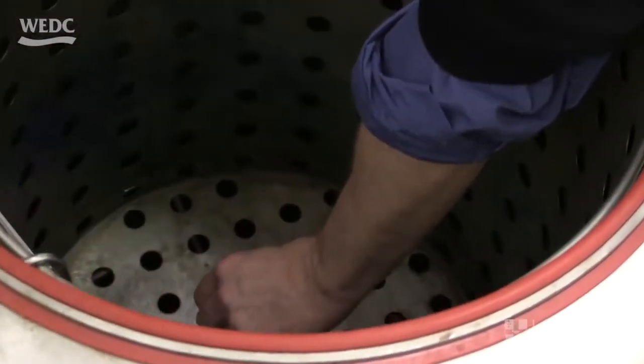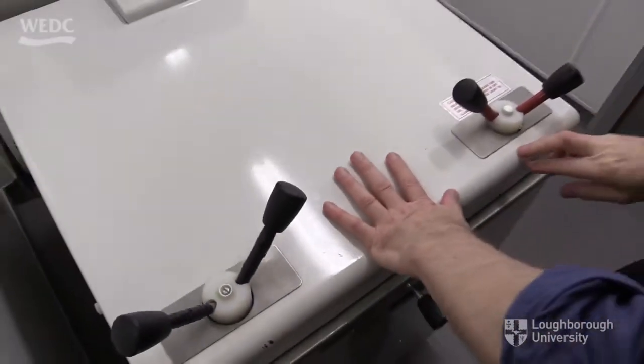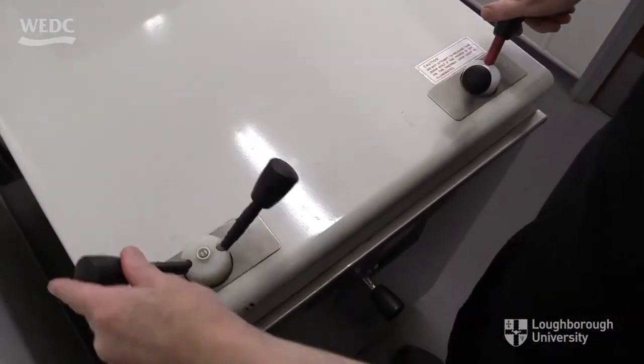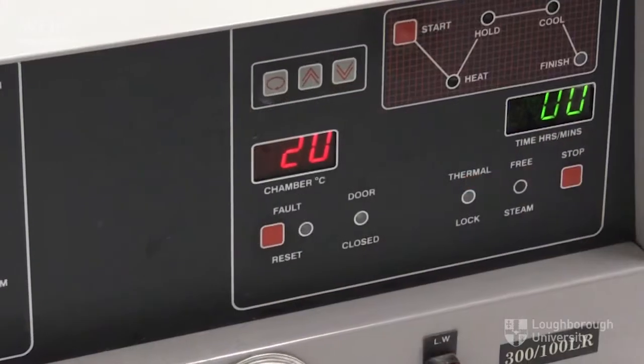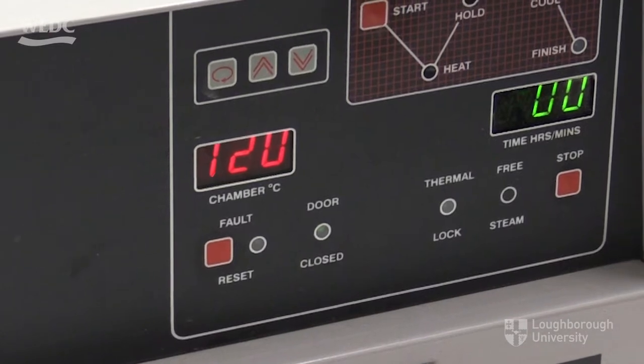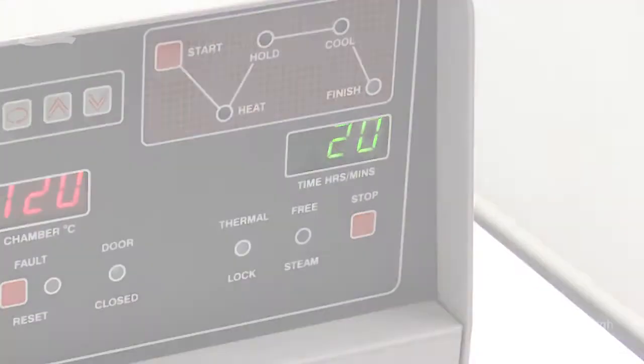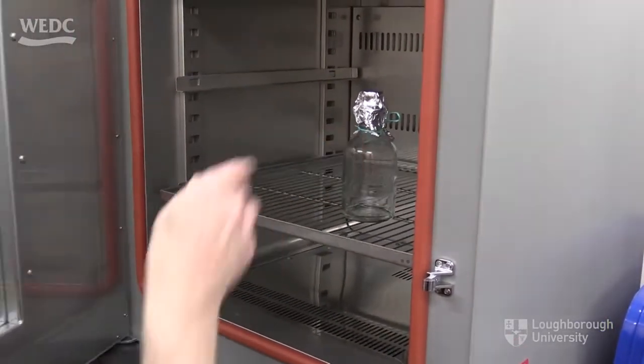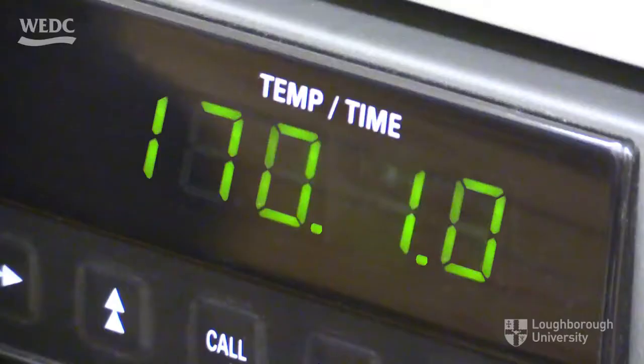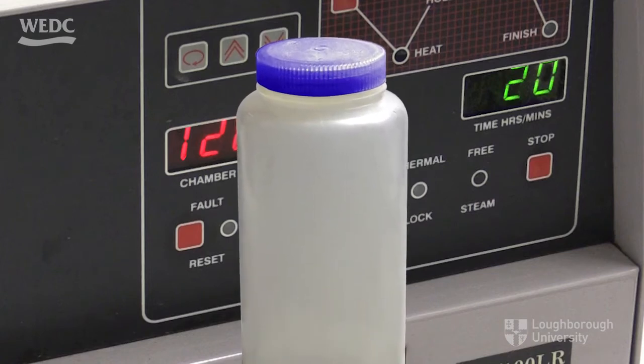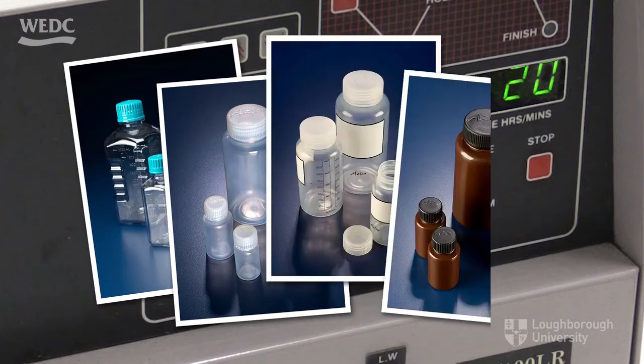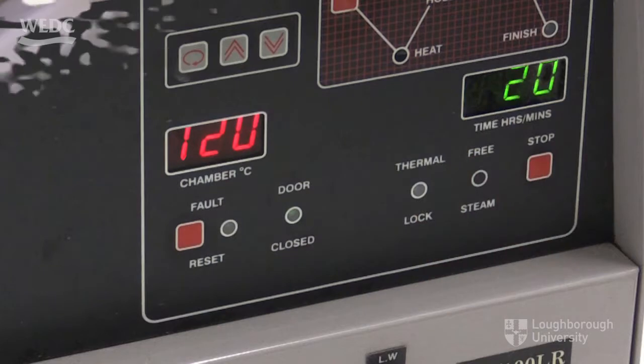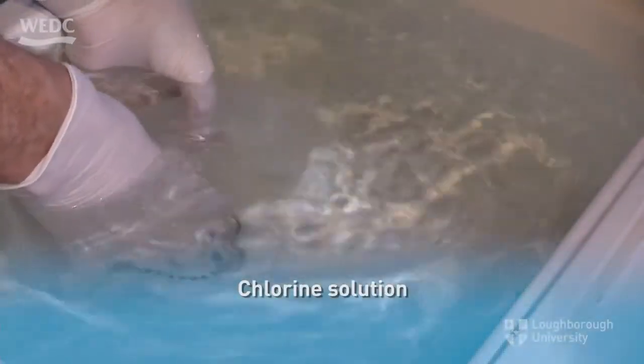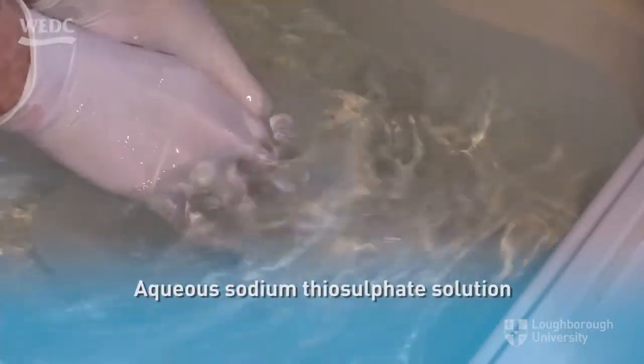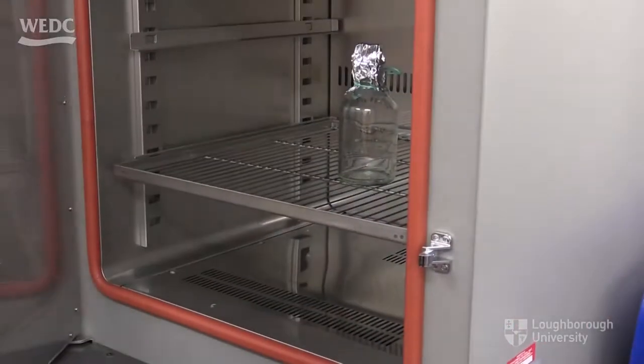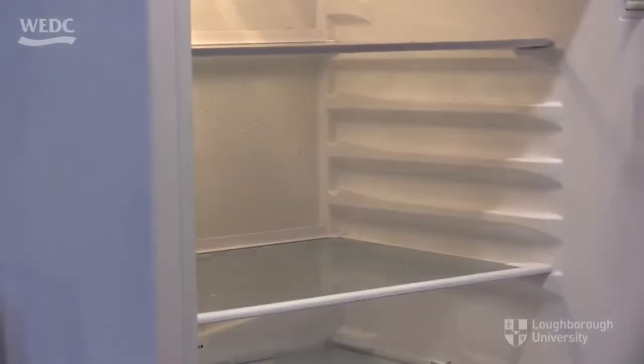Sterilize the sample bottles in an autoclave, a strong heated container used for chemical reactions and other processes including steam sterilization. Operate according to the manufacturer's instructions. Usually, bottles will require steam sterilization at 120 degrees centigrade for 20 minutes. Alternatively, glass bottles can be heated in a dry oven at 170 degrees centigrade for 1 hour. Note that most plastic sample bottles cannot be sterilized in an autoclave because of the high temperature. Special plastic bottles can be obtained, but if this is not possible, standard plastic bottles should be sterilized by immersing them in a chlorine solution at the outset, making sure that the residual is neutralized with aqueous sodium thiosulfate solution. Once sterilized, allow the bottles to cool and store in a refrigerator until required.